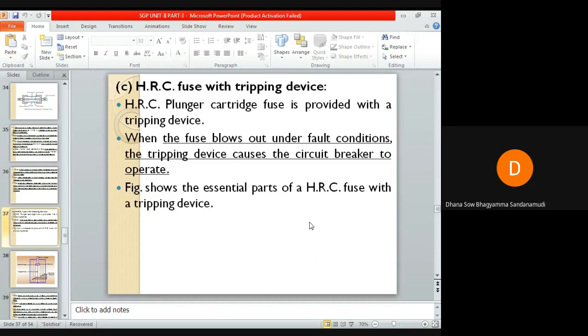We already know about the tripping device. We know the operation of a circuit breaker. The circuit breaker consists of a moving contact and a fixed contact. The moving contact of the circuit breaker will be connected to the tripping device. The tripping device is actually connected to the relay. The relay is the one which senses the fault in the circuit. Whenever a relay senses the fault, excessive current will flow in the relay coil. Hence, the trip circuit is closed. Whenever the trip circuit is closed, the trip coil gets energized. Whenever the trip coil gets energized, the moving contact of the circuit breaker will move away from the fixed contact. So the tripping device is the one which is causing the operation of the circuit breaker, meaning the circuit breaker contacts will open because of the tripping device.